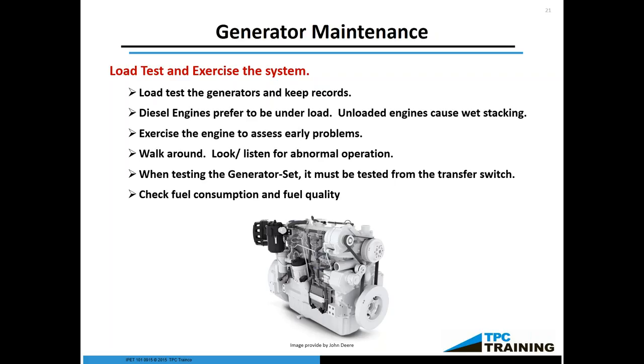If you have a lot of fuel — say a dozen backup generators each with a 10,000-gallon tank — it would be in your best interest to invest in a fuel polisher. What a fuel polisher does is basically run the fuel through a filtering system, cleaning out the water and any other contaminants. Also look at the fuel filters: you'll notice the bulbs hanging horizontally with the red fuel inside. Don't ever use green fuel — that's for agricultural use and is very illegal. But if you look at that red dyed fuel and it's cloudy, that's a bad thing — it means something's wrong with the fuel. That's what you're looking for during that 30 minutes while the engine's running: watch the fuel as it passes through the fuel filters. If it looks cloudy, you have a fuel quality issue, and that will affect the longevity of the engine.